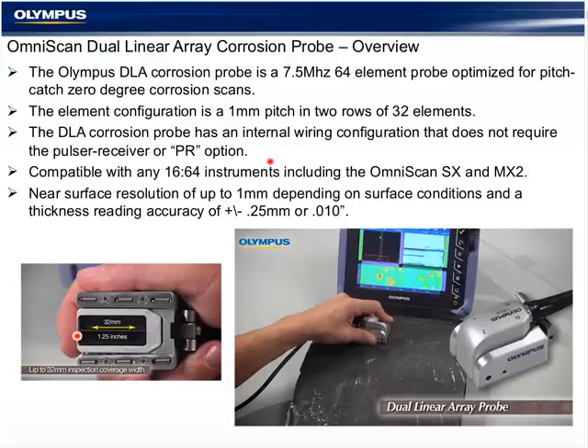The probe has an internal wiring so that it does not require the pulser receiver or PR option on your OmniScan module. A regular pulse echo instrument is compatible with this probe. Any of the 16:64 instruments, including the SX, is compatible with the probe, and it is designed with a mechanical roof angle, frequency, and aperture configuration to provide approximately 1 millimeter near surface resolution and a thickness accuracy typical of most phased array instruments without auto gain correction of approximately 0.25 millimeters or 10/1000ths of an inch.